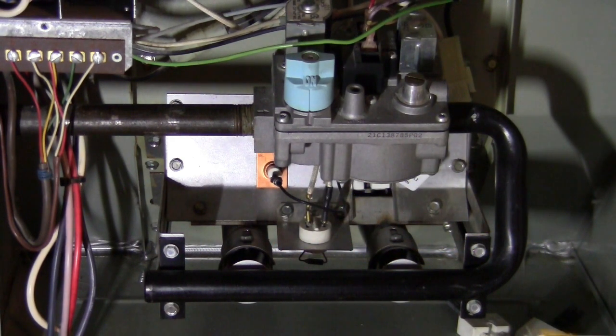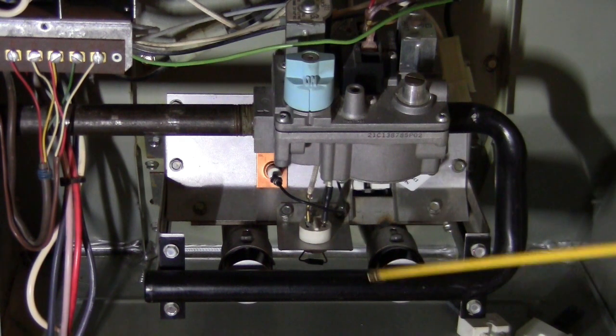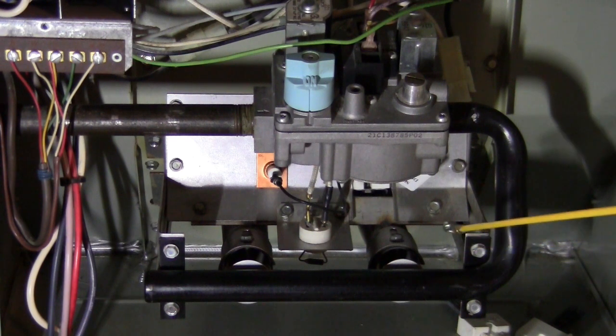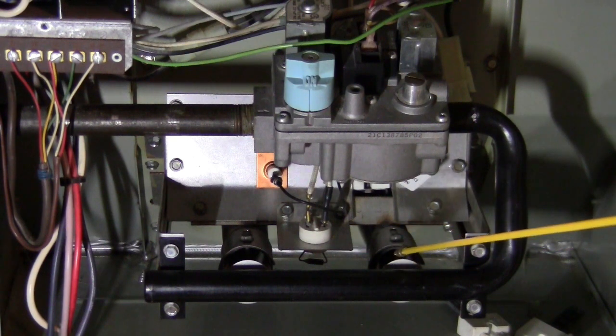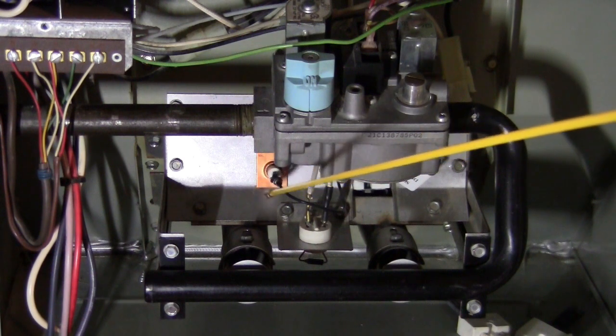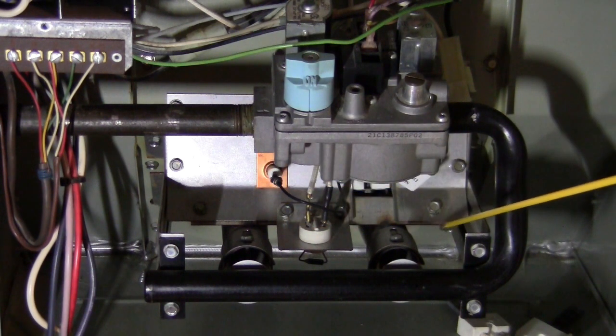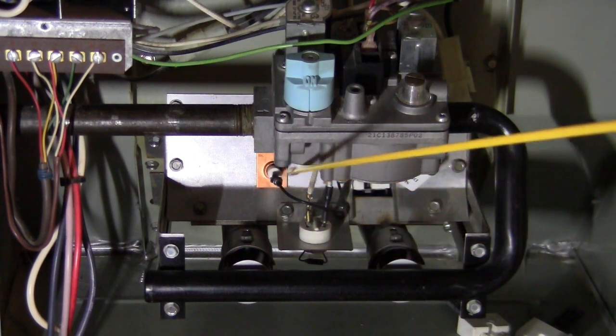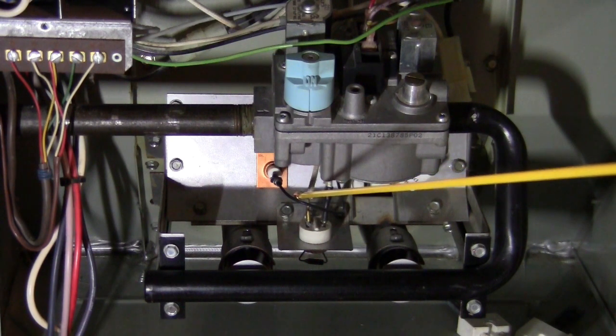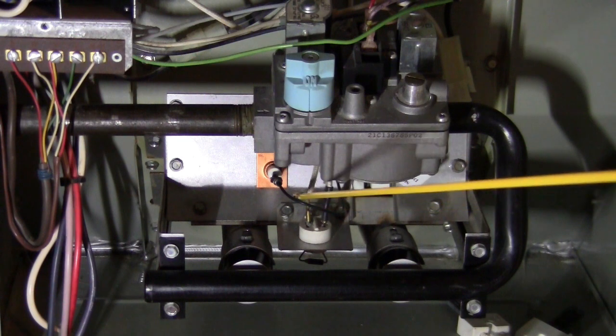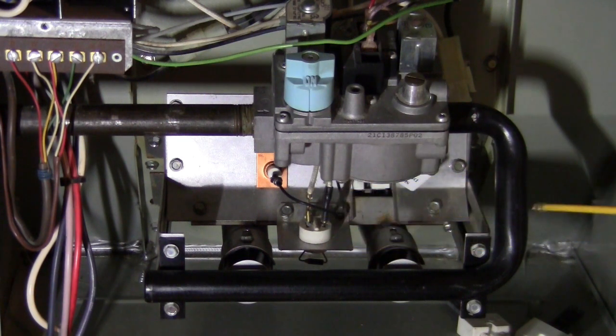But somehow, if some problem caused gas to be supplied into it but there is no fire inside, the gas is going to keep coming in, and it may cause a gas leak to the outside. The minimum situation is that you just push the gas and it blows up the chimney on top. It doesn't do anything, right? So this flame sensor is the most important. It detects that the fire is on. If the sensor does not see the fire within 4 to 5 seconds and give a signal back to the controller, it cuts off the gas.